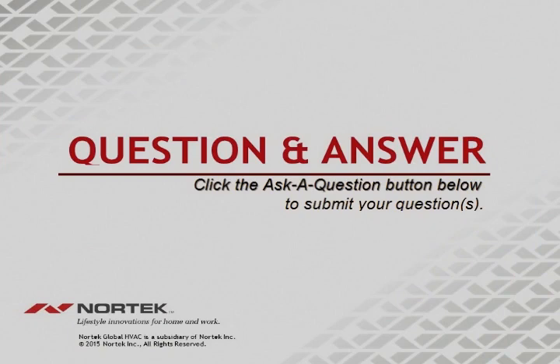The steps on how to diagnose a faulty pressure switch, vent, and condensate. Okay, that won't be something that I can really go into quickly in a lunch and learn Q&A, but the first step in terms of diagnosing a faulty pressure switch is going to be determining which, like on a 2-stage furnace, is it in low fire or high fire? Is it one of those? So, like as an example, on a 2-stage furnace, you have a grand total of 4 pressure switches, but you only have 2 circuits. So you've got 2 switches in series. You've got an inducer switch and a condensate pressure switch, and you have that for both the low fire and the high fire setup, if you will.